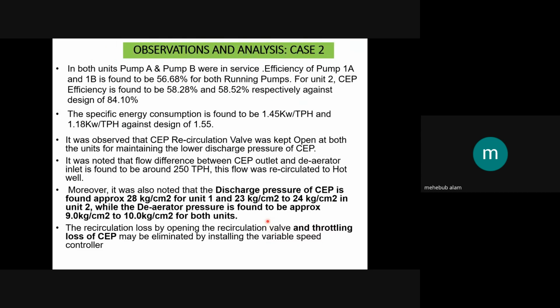But how is it identified that this pump is taking more power than required? Here we calculated the specific energy consumption of both pumps, and we observed that there is a recirculation valve, and that recirculation valve was kept open at both units for maintaining a low discharge pressure at the CEP. The discharge pressure of the condensate extraction pump was found to be 28 kg per centimeter square for unit 1, and for the second unit it was 23 to 24 kg. But the deaerator pressure was approximately 9 to 10 kg.